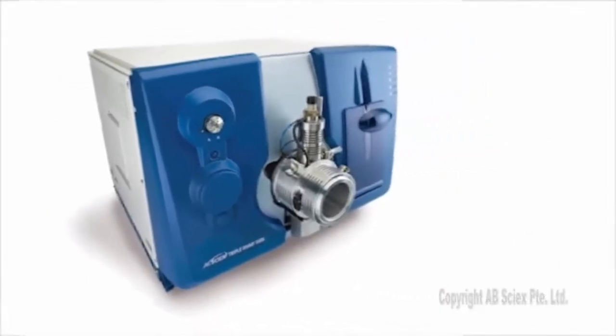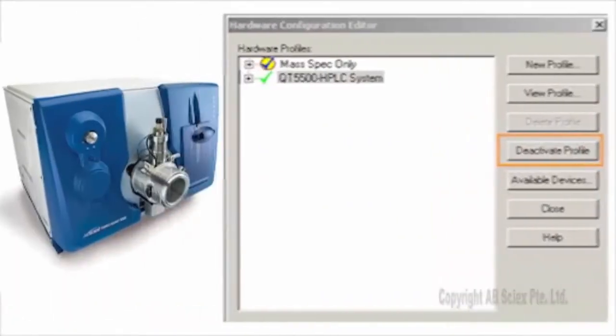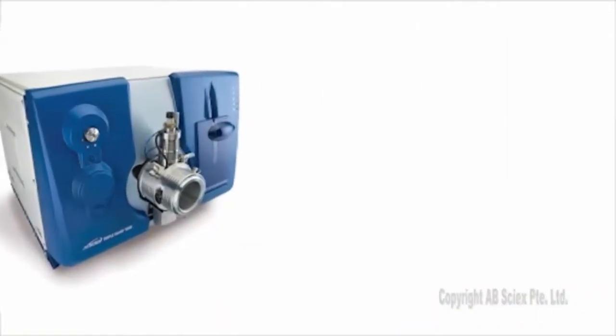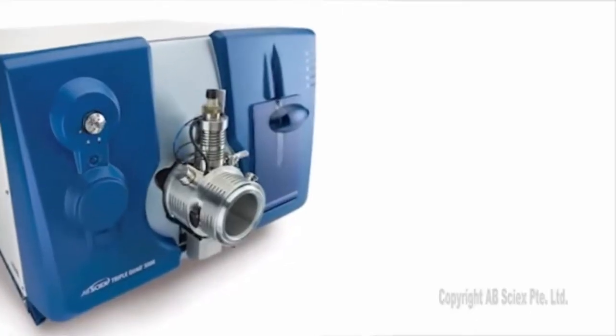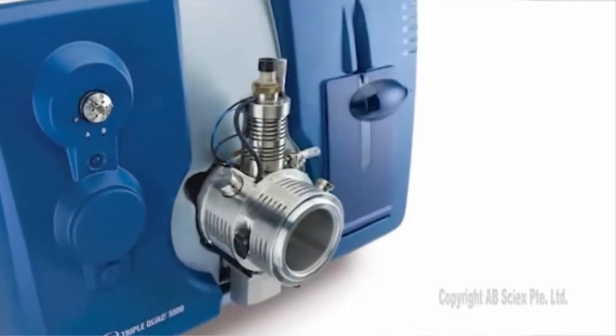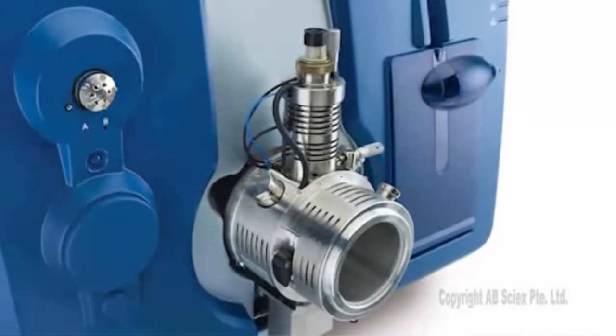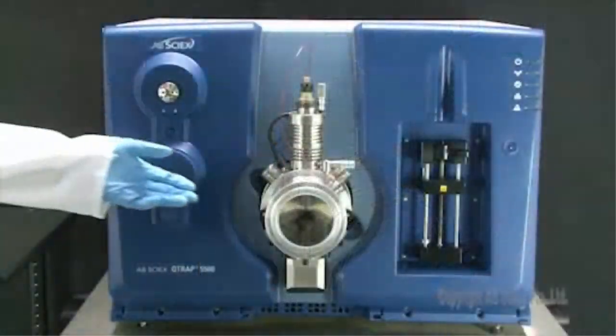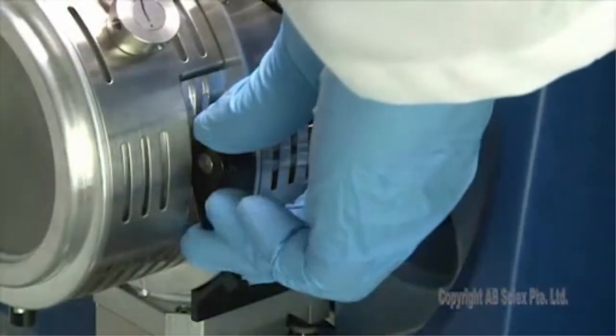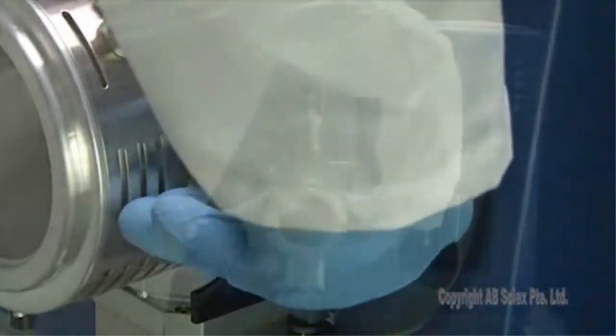Stop the sample flow and any ongoing scans. Deactivate the hardware configuration in analyst software. Wait until the source cools to room temperature. If needed, detach the sample tubing connected to the syringe pump or LC. To unlock the Turbo V source, turn both of the black latch handles 180 degrees up.